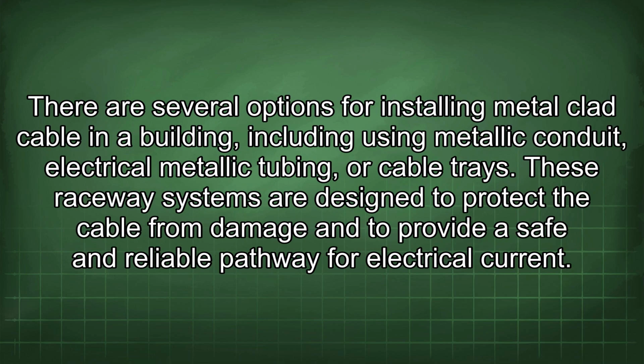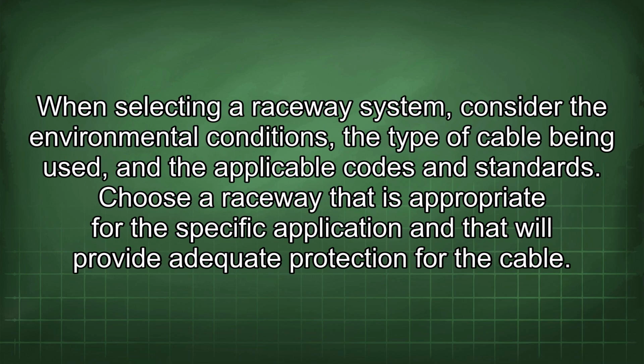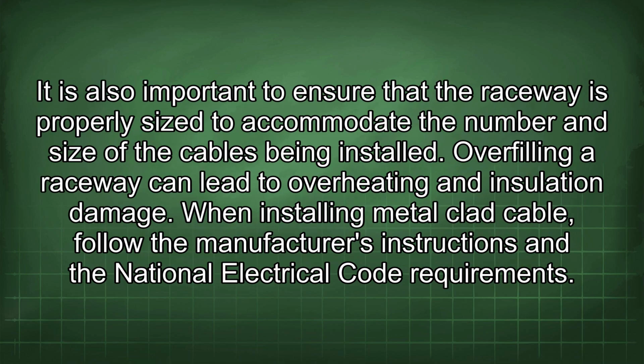There are several options for installing metal-clad cable in a building, including using metallic conduit, electrical metallic tubing, or cable trays. These raceway systems are designed to protect the cable from damage and to provide a safe and reliable pathway for electrical current. When selecting a raceway system, consider the environmental conditions, the type of cable being used, and the applicable codes and standards. Choose a raceway that is appropriate for the specific application and that will provide adequate protection for the cable. It is also important to ensure that the raceway is properly sized to accommodate the number and size of the cables being installed. Overfilling a raceway can lead to overheating and insulation damage.